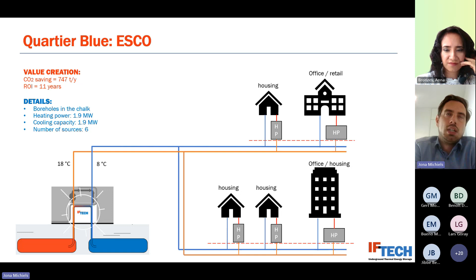Now, the system we use here, since we have multiple users - retail and dwellings, apartments - has different usage needs for heating and cooling. So we use a 3-pipe system where we supply a semi-constant temperature of about 15 to 20 degrees, which all the users use to make heating.